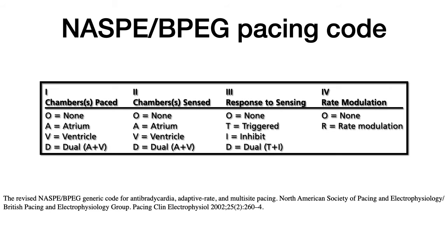The first column indicates the chamber being paced. The second represents the chamber being sensed. The third provides the pacemaker response to the sensed ventricular activity. And the fourth contains the letter R, which indicates whether rate adaptive or rate responsive pacing is being used or not. The rate responsive pacing responds to sensors in the pacemaker that increase the heart rate during physical activity. The currently available rate adaptive sensors are the accelerometers that respond to movement and the minute ventilation sensors that respond to the increase in the respiratory rate.